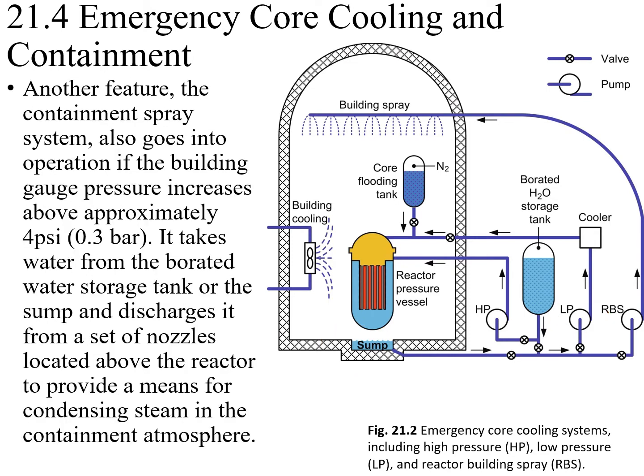Another feature is the containment spray system. This one goes into operation if the building gauge pressure increases above approximately 4 psi or 0.3 bar. It can take the water from the borated water storage tank, and discharge it from a set of nozzles located above the reactor to provide a means for condensing steam in the containment atmosphere.